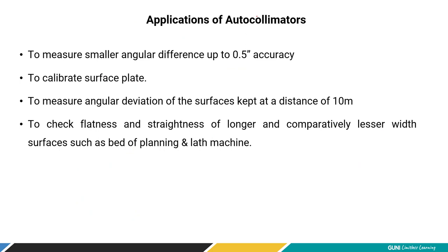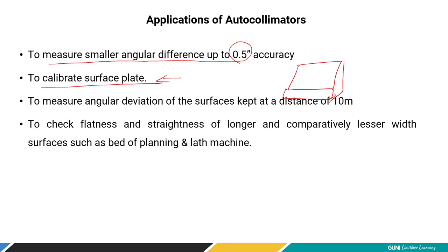The autocollimator is used to measure smaller angular differences up to 0.5 seconds. It is also used to calibrate surface plates — which is very important in the metrology lab and workshop where granite surface plates can be one to two meters in size. For calibrating flatness and straightness of such plates, the autocollimator is widely used. Basically, the autocollimator is used as a calibrating tool for finding angular deviations.